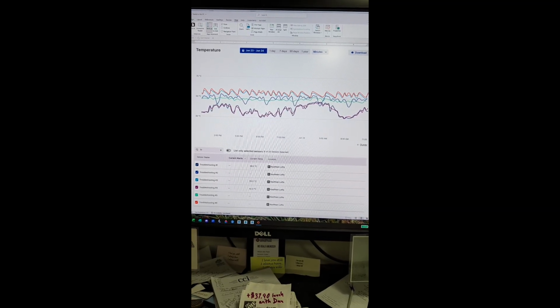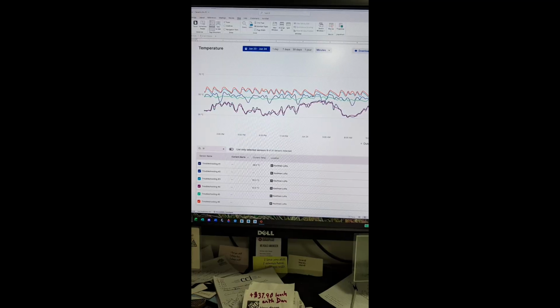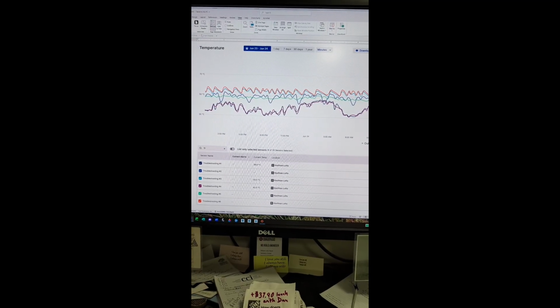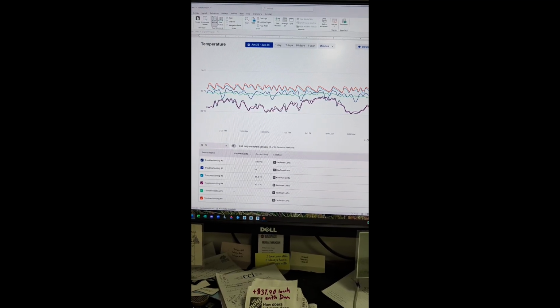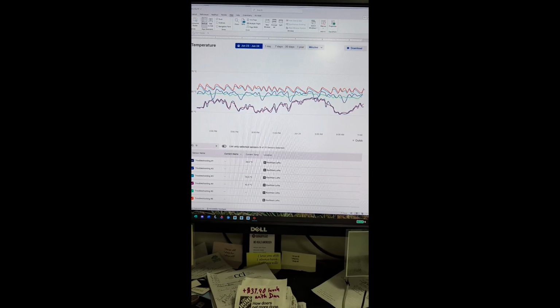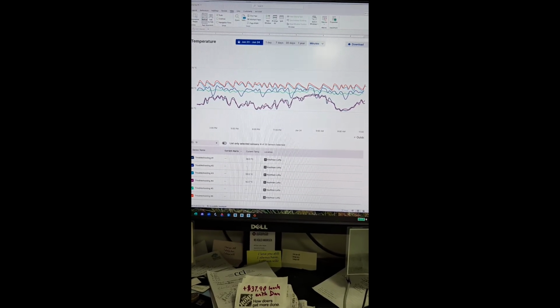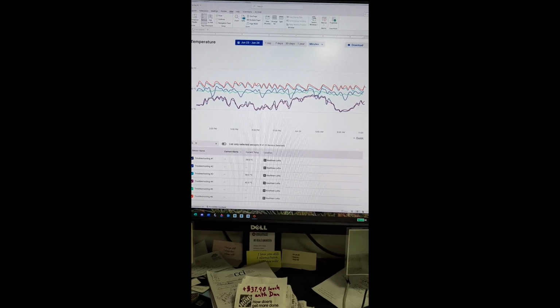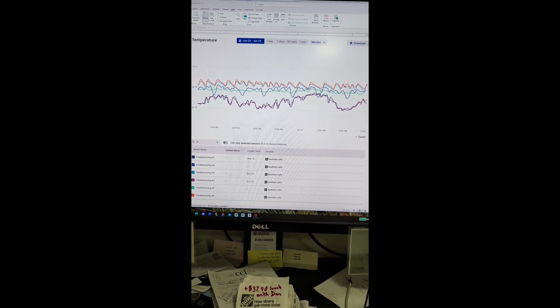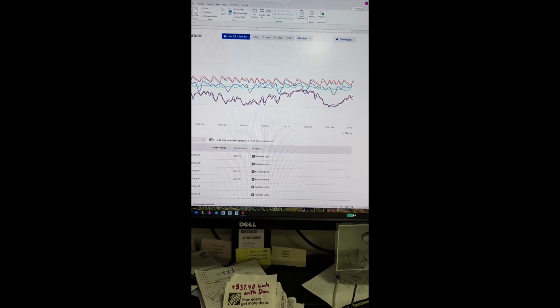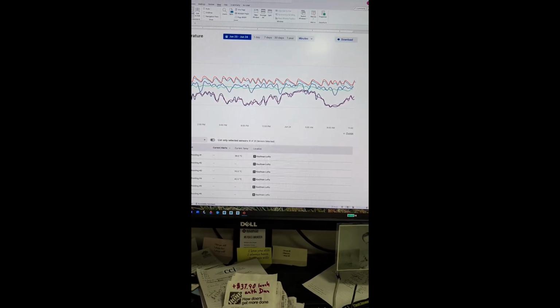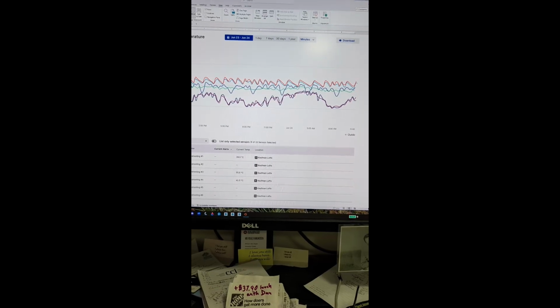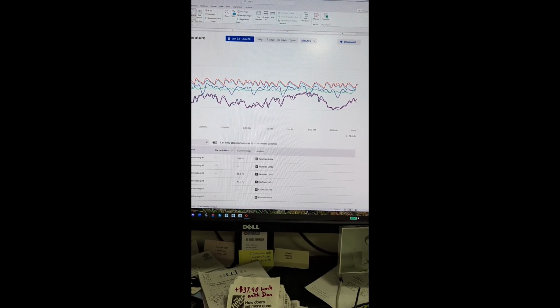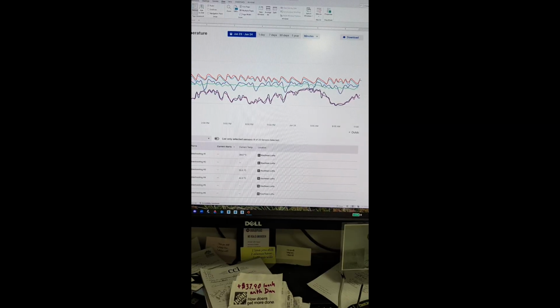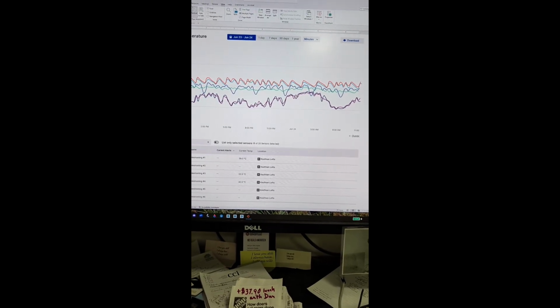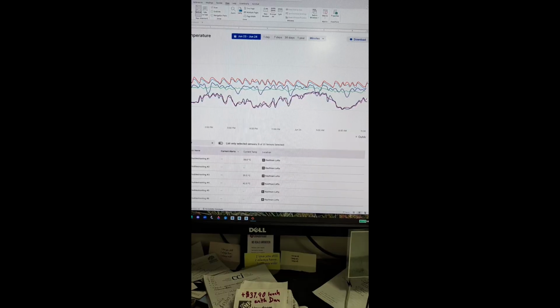This is normal operation. You can see the cold water coming in increases a little during the afternoon, and even more on the right side of the chart, which is the overnight hours. This is normal because in a large multi-residential building, hot water typically circulates past all the units so it's always available. Some of that hot water mixes back into the cold water feed of the mixing valves, and when there's very low flow, the mixed-in hot water raises the temperature. We can look at this and say everything's working the way it should.